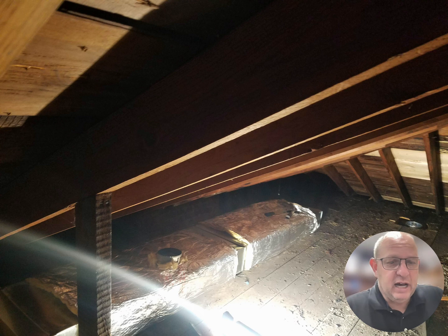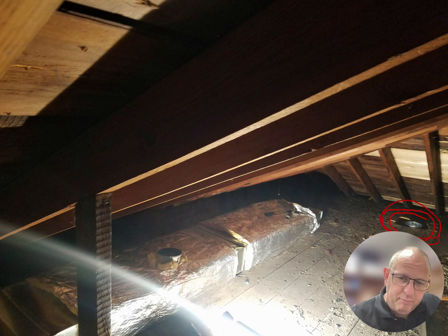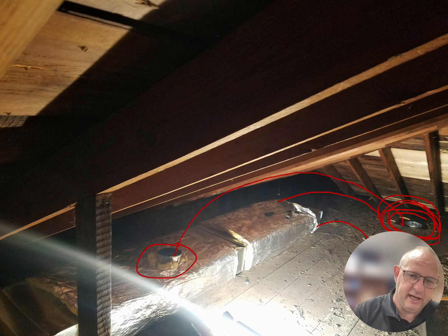Now, as you can see, I have placed that ductwork in the vicinity as I'm running it over. You guys can see it right here in the corner of it. I have placed a boot, a straight boot, going straight down into the environment that I wish to put the airflow in. I'm going to use a horizontal 90, and I'm going to come across and go this direction, and I'm going to use flex duct that I'm going to attach to my takeoffs that I've run here, and I'm going to run it above the ductwork and then into that, and then continue this ductwork out to the right beyond the picture that you guys are seeing right here.